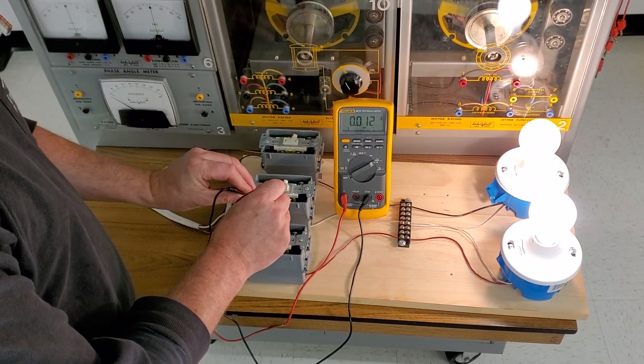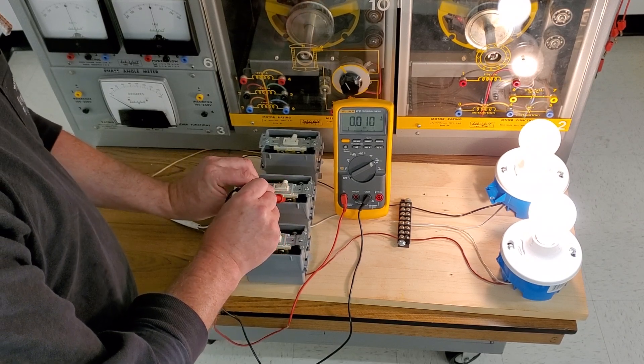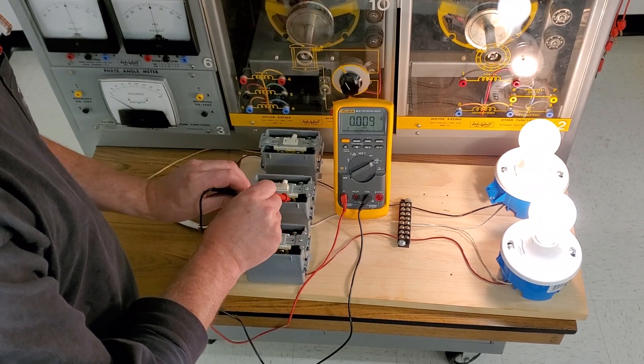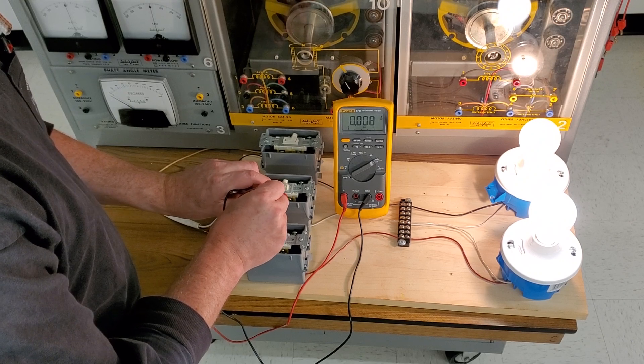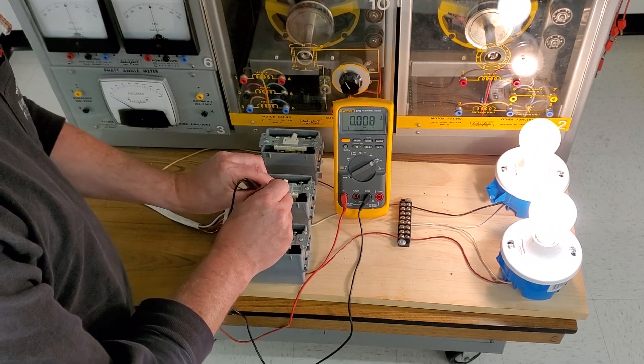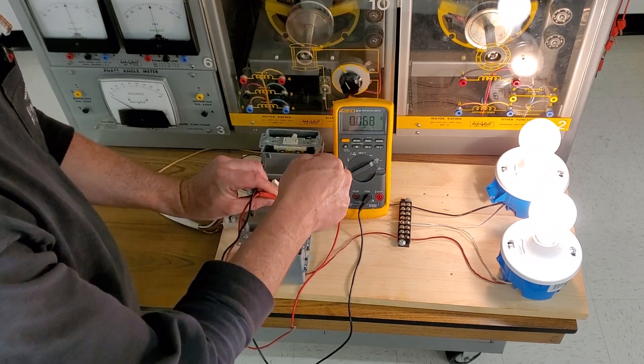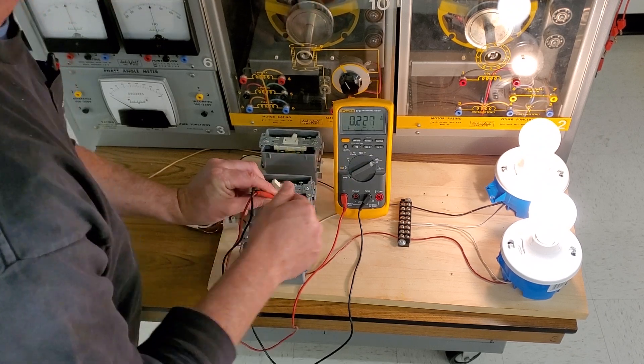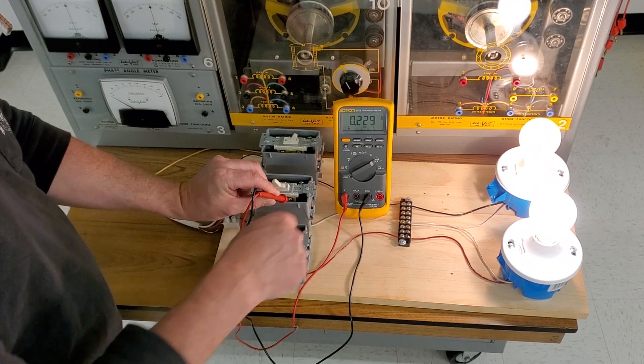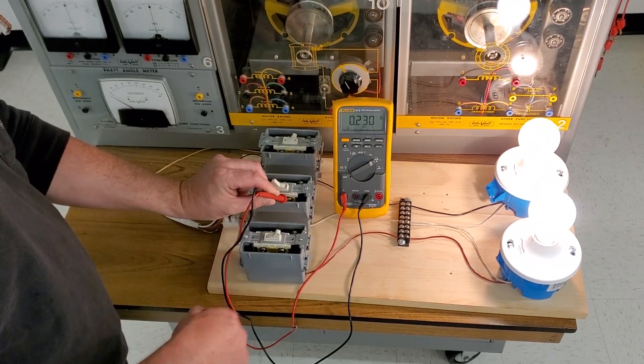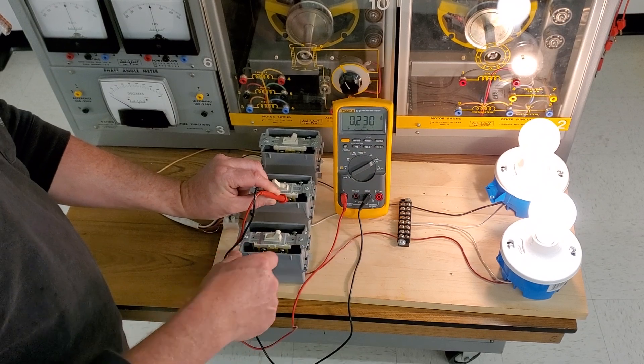But because this is a three-phase system and we're only using two out of the three phases, we're actually reading the sum of the total current here, which is 0.229 or about 0.23. This guy and this guy aren't canceling each other out on the neutral.